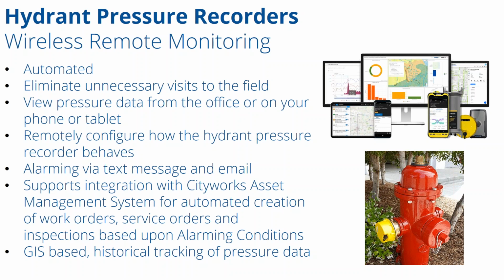We can alarm based upon a problem. You configure what that problem is based upon PSI, and an alarming condition can be set so we send you a text message and an email, or either one, whenever there's a problem. It's very easy to set up who gets those text message or email alarms, based on a couple of different conditions I'll show you in a moment.